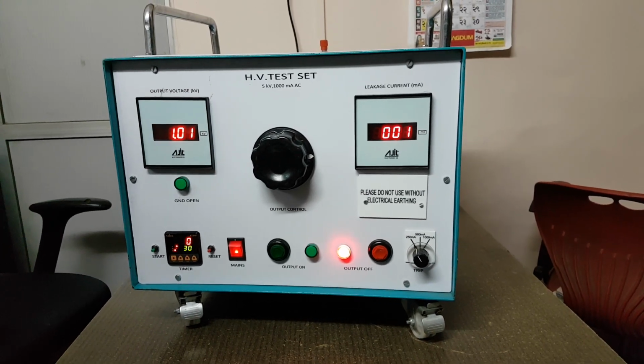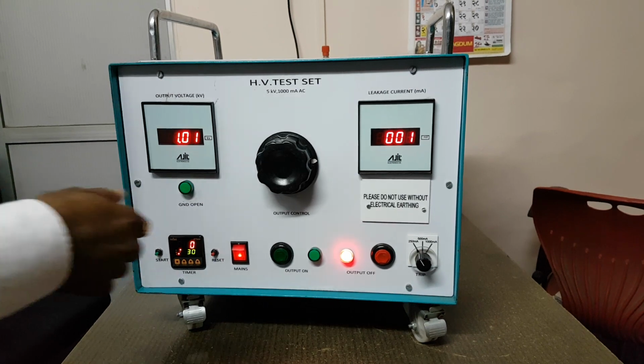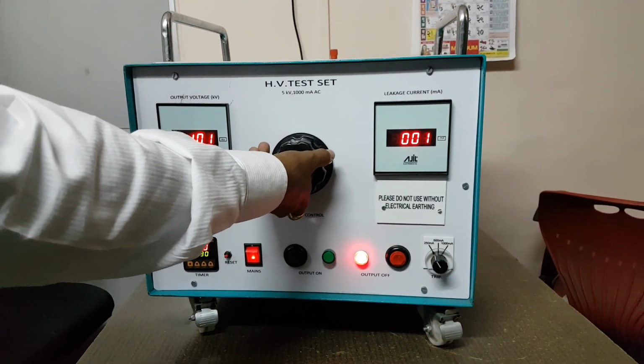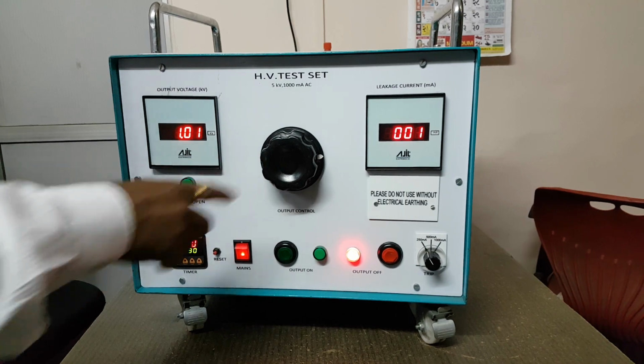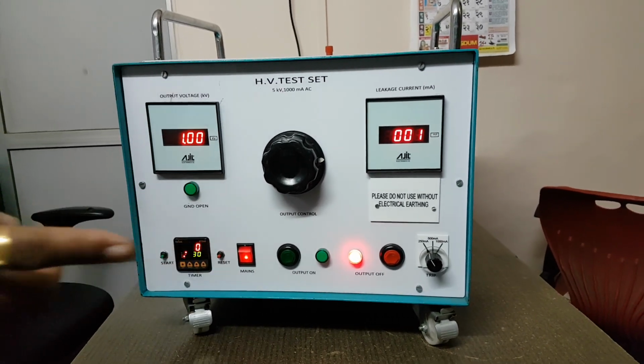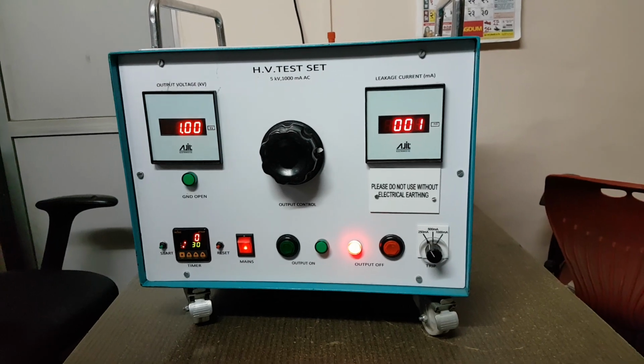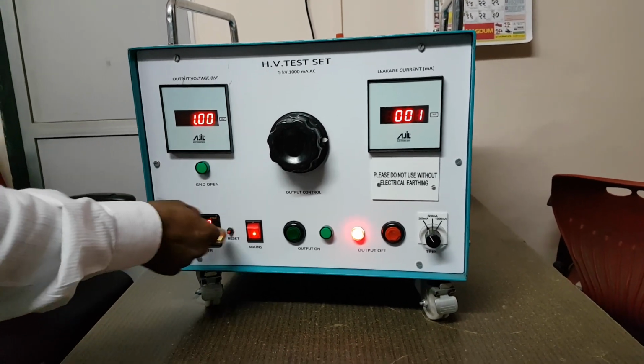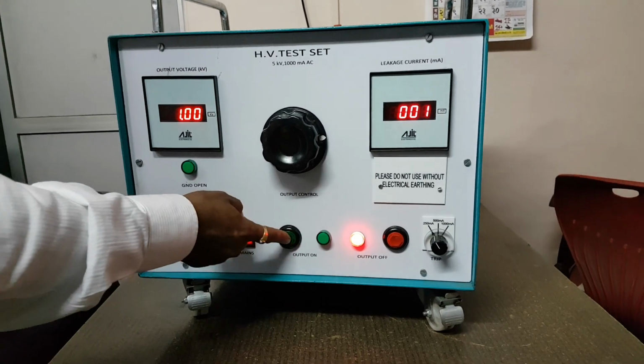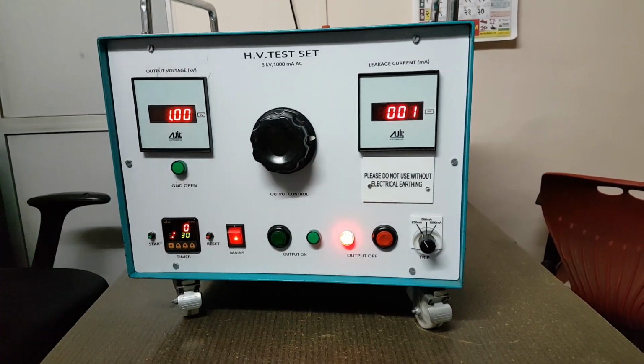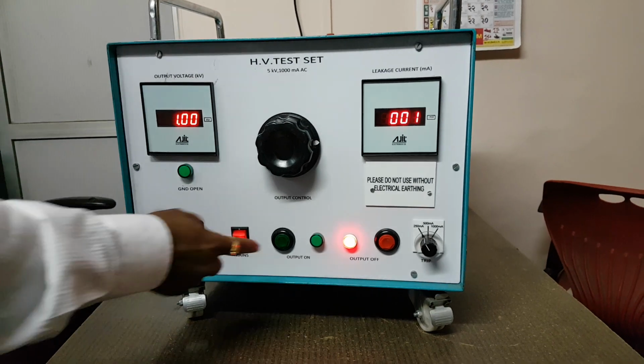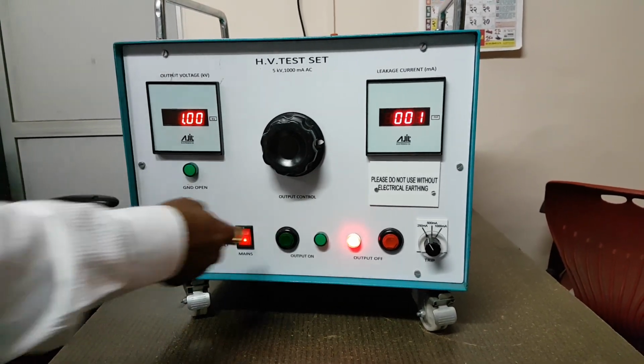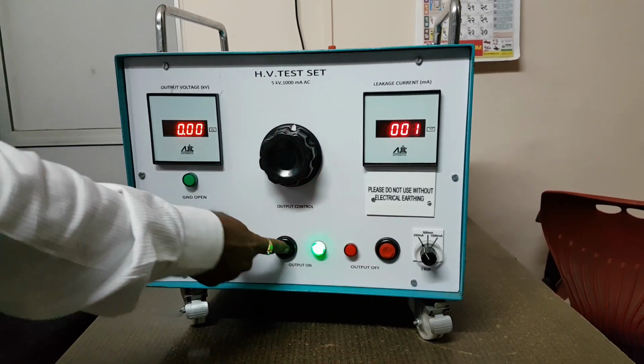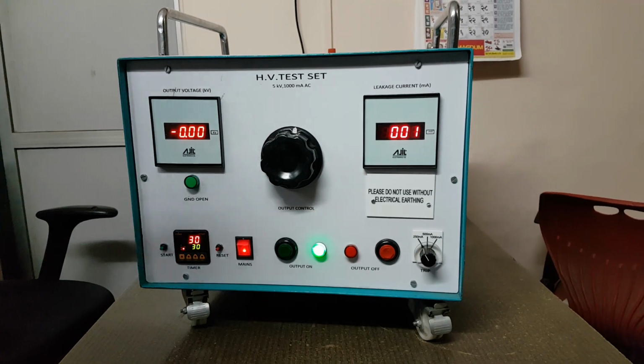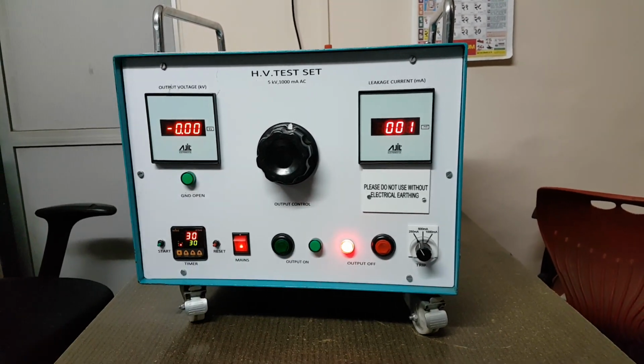That is one. To start another test, we have to bring this dimmer to 0. One thing, we have to reset this timer again, otherwise the output cannot be started, like this. Suppose we have not reset this, we are trying to put the output on, it will not. So reset. Again we are trying, it will not get on. So we have to bring this dimmer to 0. Now we can take a second test, like this. So this is all about the high voltage tester.